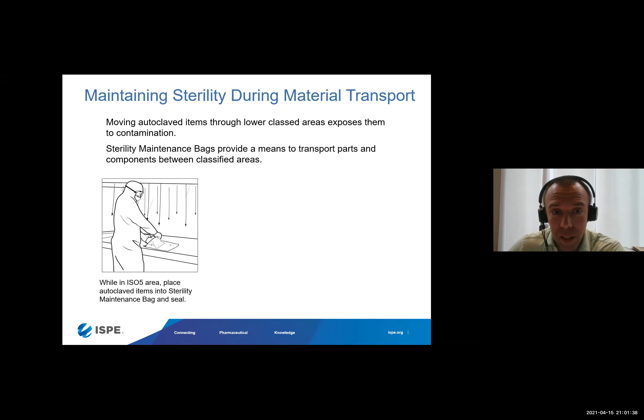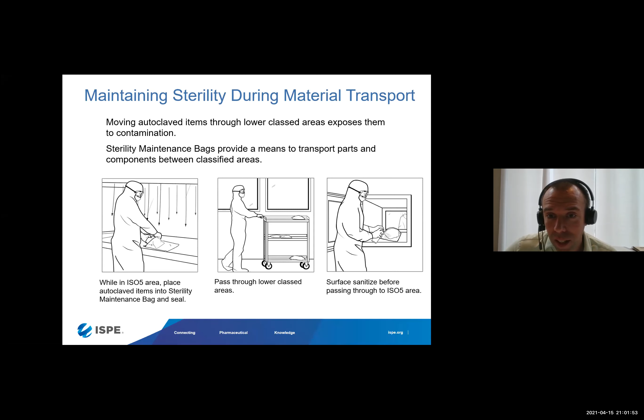This secondary protection is perfect if these items are passed through a lower classified area during transport. The surface can be sanitized in the material handling airlock. The sterility maintenance bag captures the environment during unload. So typically the autoclave unload is in an ISO 5 area. The bag would be sealed up, capturing that ISO 5 area. If the materials are then transferred through maybe an ISO 6 or an ISO 8 area, the sterile parts inside would not be exposed to that lesser classification.